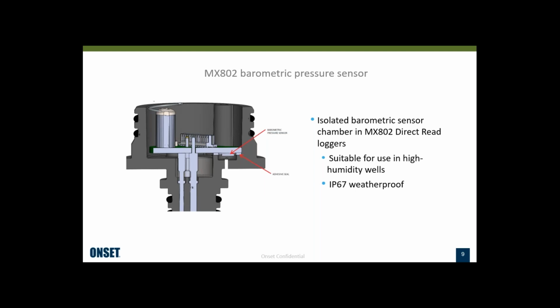There is a Gore-Tex membrane over the barometric pressure sensor to protect it if it temporarily gets dunked in the water. There's no water that's going to get into the logger, so it provides temporary protection. We do not recommend submerging these loggers. We rate them as IP67, and they are very weatherproof.